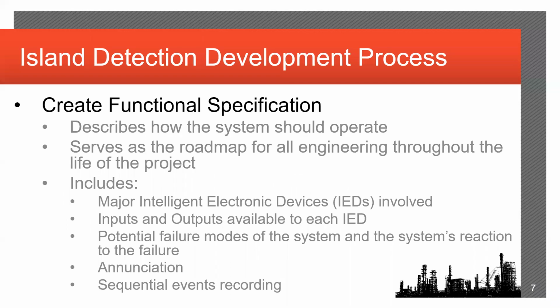At the outset of the project, the first thing we did was create a functional specification. This document describes in a narrative exactly what the intent of the island detection system was supposed to do and how it operates. It also serves as the roadmap for all of the engineering that came after that. In addition to the narrative, it also lists all of the major IEDs involved in the system, all the I/O connected to each IED, potential failure modes of the system, and the desired reaction of the system to those failures, annunciation, and then of course the sequential events recording for testing and troubleshooting and that sort of thing.